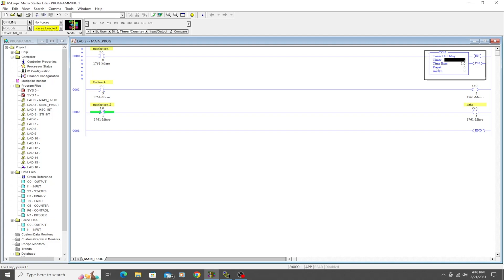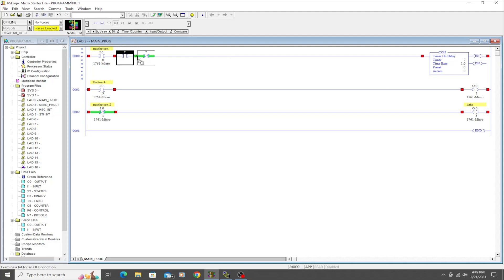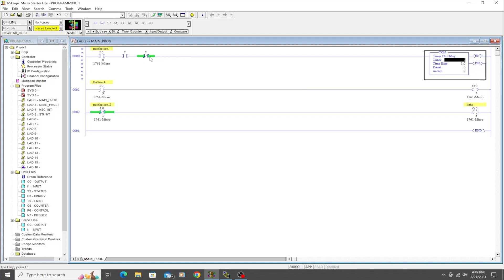These timers do need to be—the timer instruction itself at least does need to be on the right-hand side and needs to act like an output. You can have different types of bits through here that are going to control this timer. So what I mean is you could have several different bits here that need to become true for this timer to come on. But in this case, we're going to keep it simple and just have this single push button that is going to activate this timer.